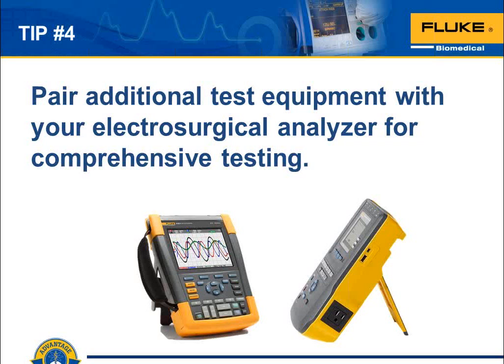Don't forget, you should be testing applied parts. So the active electrode, cut and coag, those are all applied parts. Those need to be tested, included in your electrical safety leakage current test. Most manufacturer performance inspection procedures require both high frequency leakage and regular leakage current testing.